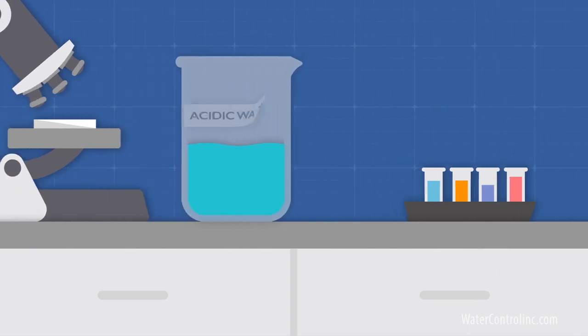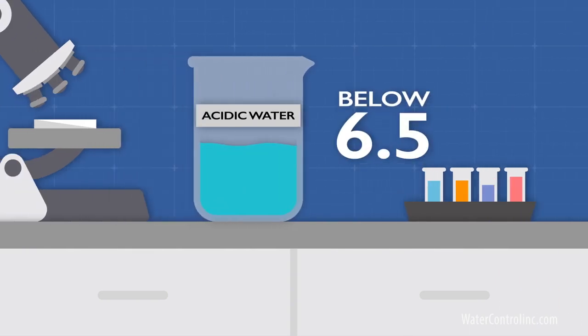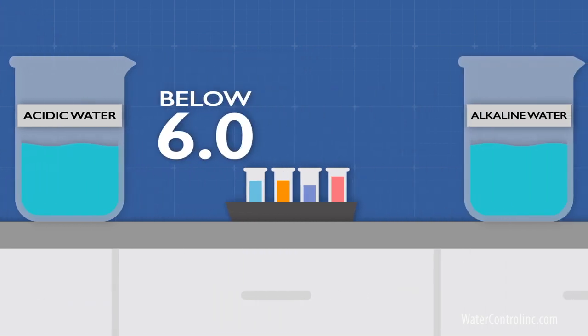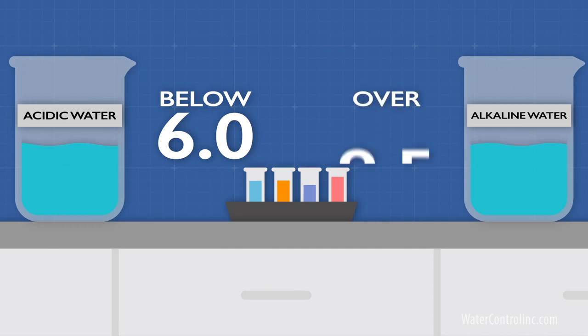Acidic water is a problem. It corrodes piping, valves, fittings, and equipment. Problems can start when pH falls below 6.5, and will be significant when it falls below 6.0. Alkaline water can also be corrosive, particularly if the pH rises over 9.5.